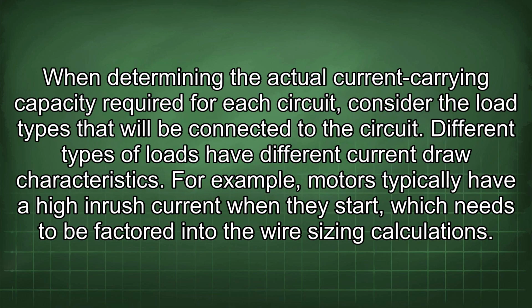When determining the actual current carrying capacity required for each circuit, consider the load types that will be connected to the circuit. Different types of loads have different current draw characteristics. For example, motors typically have a high inrush current when they start, which needs to be factored into the wire sizing calculations.